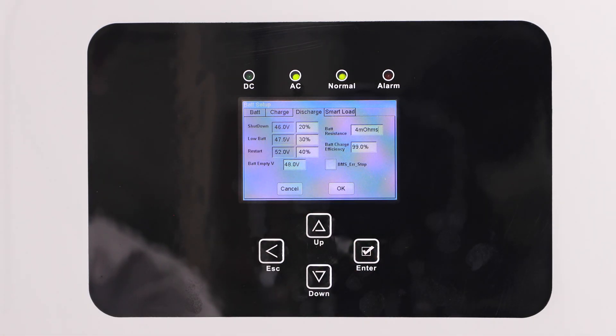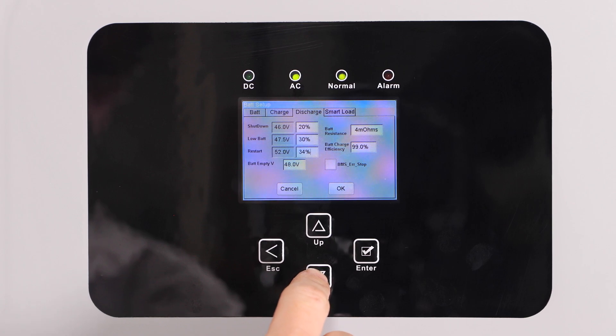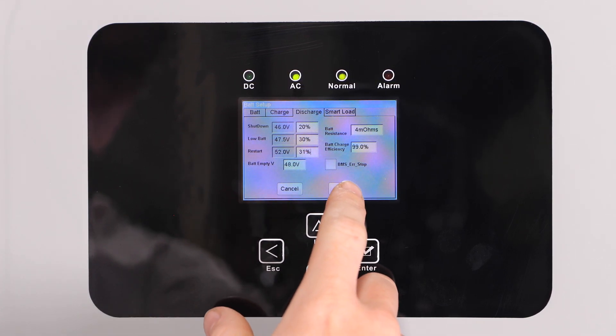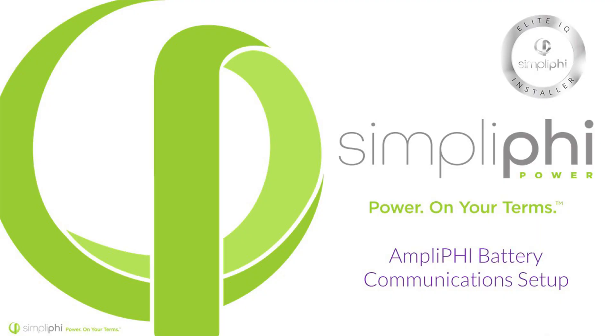Set the shutdown to 20%, low battery to 30%, and restart to 31%. Set the battery empty voltage to 48 and press OK to save your settings.